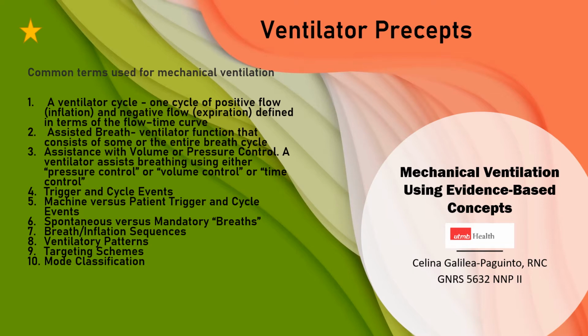The servo targeting scheme is a scheme in which the output of the ventilator automatically follows a varying input. Current examples for neonatal ventilation is the NAVA, or Neurally Adjusted Ventilatory Assist. The adaptive scheme is a targeting scheme that allows the ventilator to automatically set one target. Modes that use pressure control with adaptive targeting are often referred to in the literature as volume-targeted or volume guarantee modes.